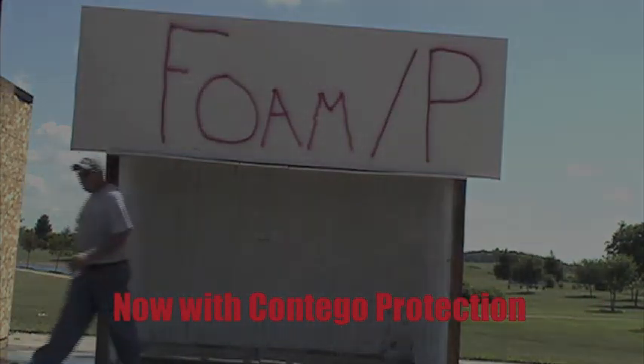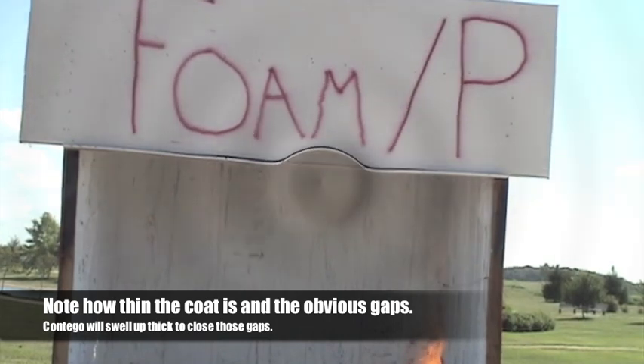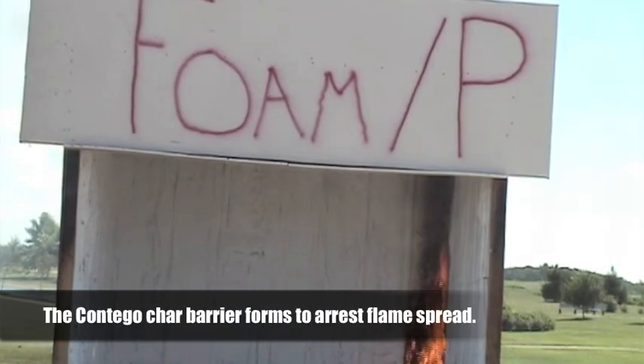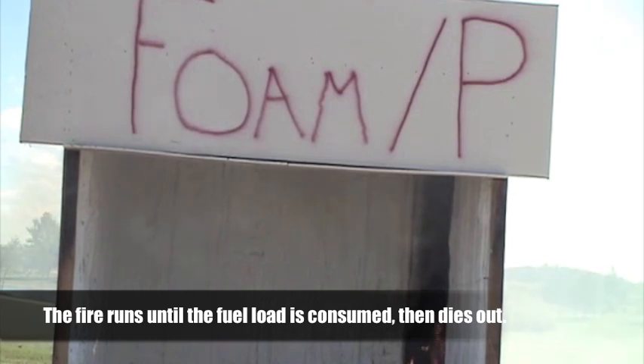Now we'll run the same sequence, beginning with the same small fuel load. Note how thinly the Contego coating is applied — you can see big gaps running up and down the walls, and you can almost see through the Contego coating to the foam underneath. But no problem: the Contego coating will swell up to close those gaps. The walls are scorched, but the fire can't get to the fuel that it needs, so it simply dies out.